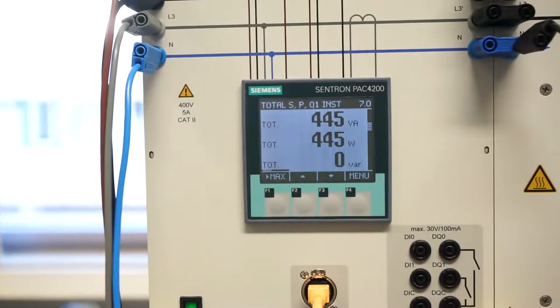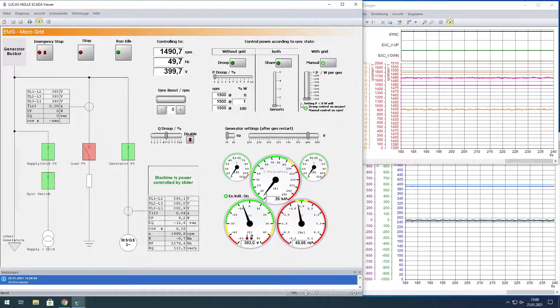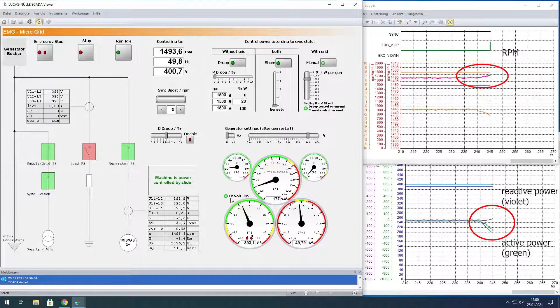As you can see, the frequency is about 49.7 Hertz, since the primary control of the simulated generator is active. Now, let us increase the power infeed from the real synchronous generator. Since the generated load is increased, the simulated load will be decreased. So the frequency will rise due to the mentioned PF droop curve.